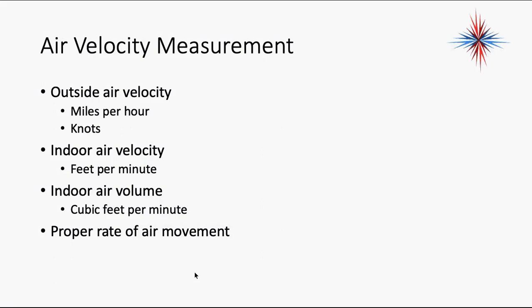The magic number is 400. Per ton of air conditioning, I have to move 400 CFM of air. But it has to be at the proper speed as well.